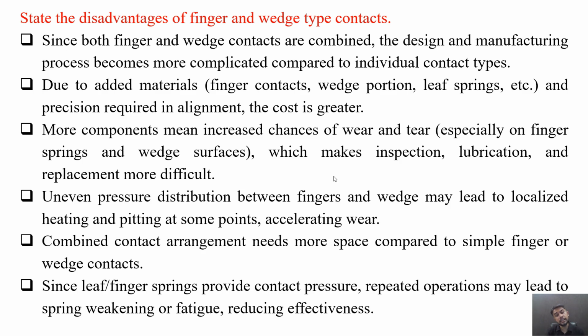More components mean increased chances of wear and tear, especially on finger springs and wedge surfaces, which makes inspection, lubrication, and replacement more difficult. Uneven pressure distribution between fingers and wedge may lead to localized heating and pitting at some point, accelerating wear. The combined contact arrangement needs more space compared to simple finger or wedge contacts. Since leaf or finger springs provide contact pressure, repeated operations may lead to spring weakening or fatigue, reducing effectiveness. So these are several disadvantages of finger and wedge type contacts of a circuit breaker.